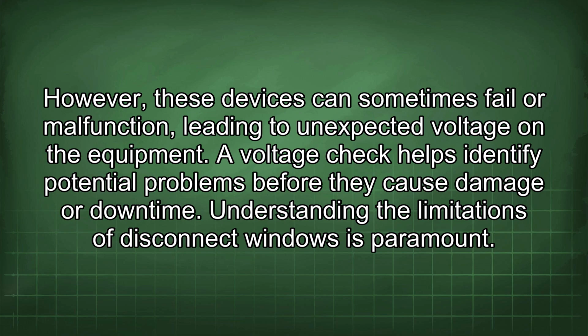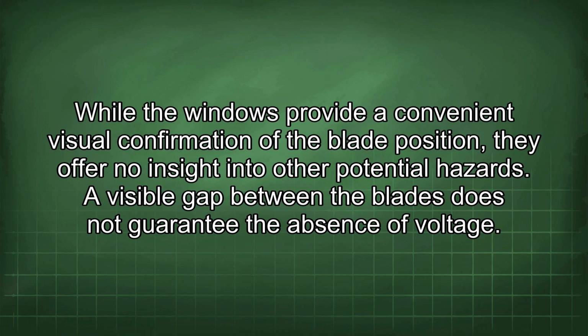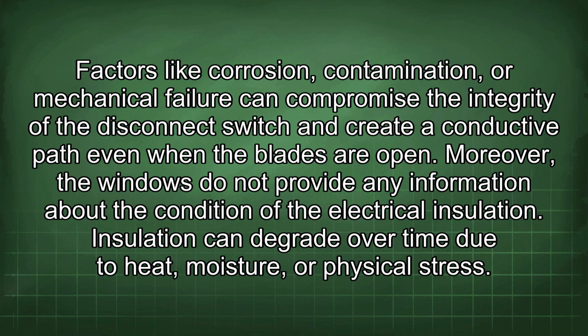Understanding the limitations of disconnect windows is paramount. While the windows provide a convenient visual confirmation of the blade position, they offer no insight into other potential hazards. A visible gap between the blades does not guarantee the absence of voltage. Factors like corrosion, contamination, or mechanical failure can compromise the integrity of the disconnect switch and create a conductive path even when the blades are open.